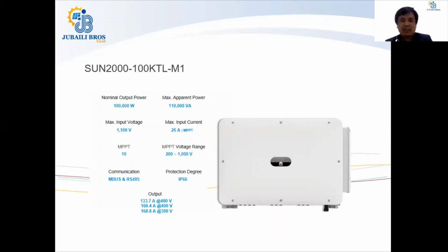MPPTs with this inverter are 10, which is the highest number of MPPTs in any Huawei inverter. The MPPT voltage ranges from 200 volt to 1000 volt. Now, when you are designing your PV system, normally try to keep in consideration that there is a good voltage range, which is like 450 up to 800.